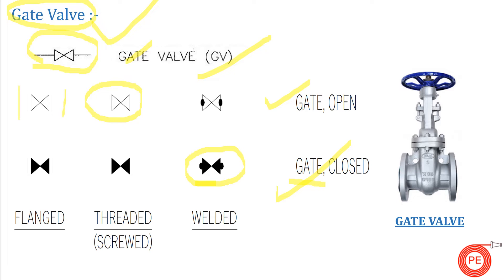For end connections: if there are two lines beside the valve symbol, the valve is flanged. If there is nothing beside the valve symbol, the valve is threaded. If there are two dots on the end of the valve, the valve is welded. These symbols may vary slightly from designer to designer, but the basic symbol remains the same.